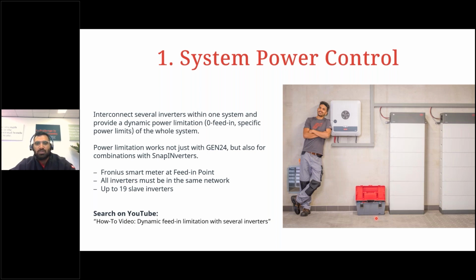They must be on the same network, and you can connect up to 19 slave inverters to one master, which has the meter connected. So in total, you can have up to 20 inverters. You could search the YouTube how-to video on dynamic feed-in limitation with several inverters to know more about how to set this up.